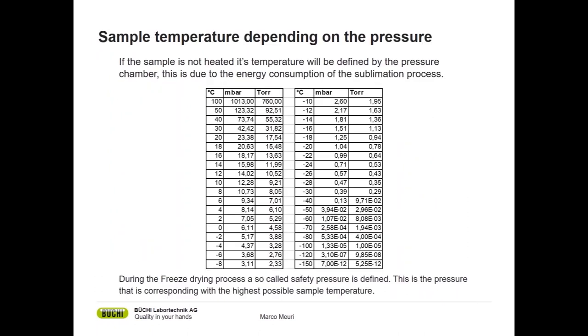When we look at the parameters of freeze drying, the most important parameter is definitely the pressure — the pressure in the system. In freeze drying, we use low pressures, and importantly, the pressure will define and control the sample temperature during freeze drying. If you look at the table on this slide, this is for purely aqueous systems.